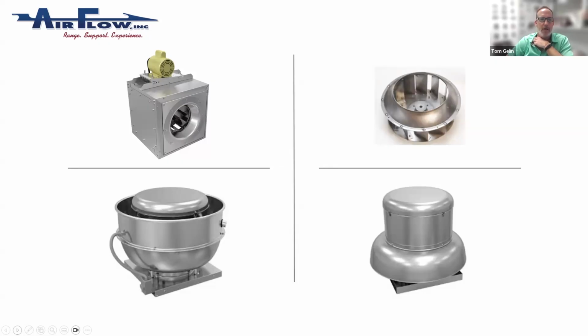After a while you realize it doesn't really matter if the centrifugal wheel is driven by a belt or a direct drive motor, or whether it's in an inline fan, an upblast fan, a downblast fan, or some other configuration. The principle of that centrifugal wheel is it moves a modest amount of airflow against a modest amount of static pressure. Having the fundamentals makes it easier to understand what the product does.